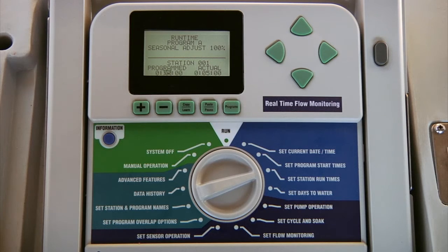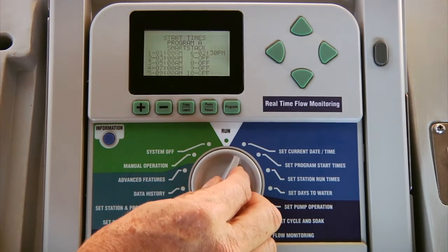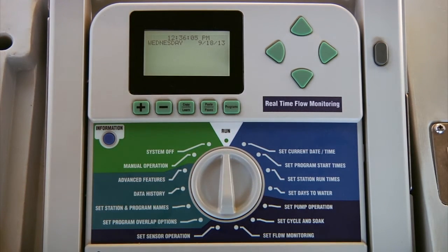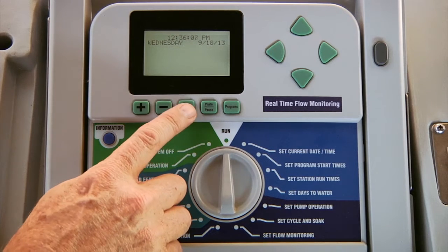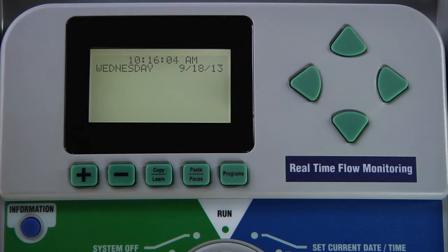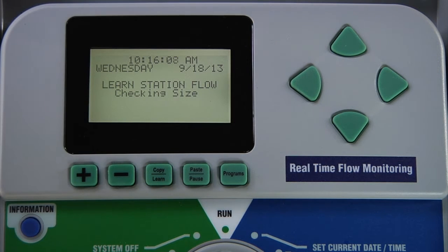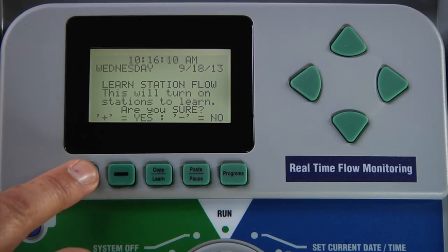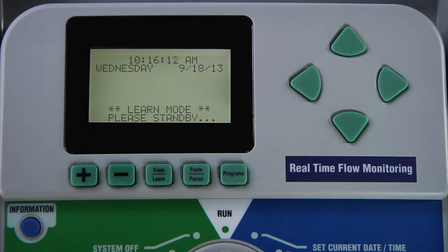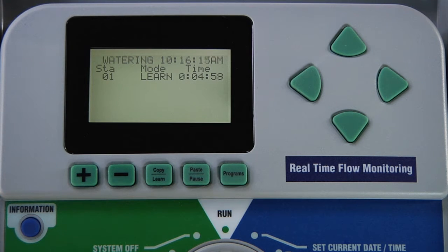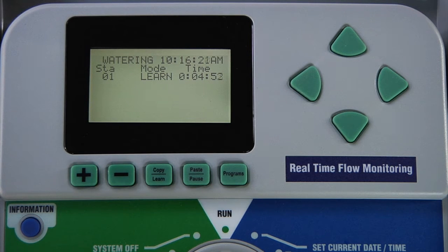Once you have verified that the desired stations have run times, turn the dial back to the run position and press the copy learn button. The display will ask you if you want the learning process to begin. Press the plus button to confirm. The controller will start learning the flow for each one of the stations. Each station can take from 35 seconds to 5 minutes to be learned depending on the stability of the flow. This process may take a full hour or longer for a 42 station system. Make sure you don't disturb the controller during the learning process.